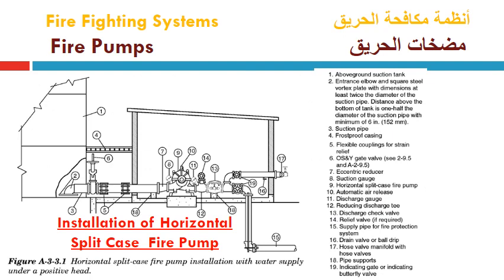This slide shows a typical installation of a horizontal split case fire pump as per NFPA 20, when using a horizontal split case fire pump supplied with water from a water supply tank under a positive head, which is named static suction head. All the numbers are shown in the table on the right hand side, starting from number 1, above ground suction tank, with this free water surface which provides static suction head above the center line of the pump.